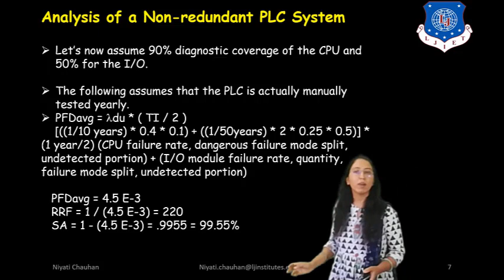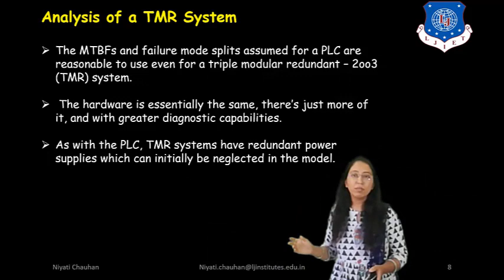Thereafter, next is analysis of a TMR system. The MTBF and failure mode splits assumed for the PLC are reasonable to use even for a triple modular redundant 2 out of 3 TMR system. The hardware is essentially the same, there's just more of it and with greater diagnostic capabilities. As with the PLC, TMR systems have redundant power supplies which can initially be neglected in the model.